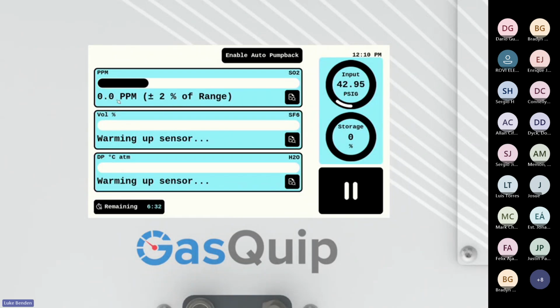Right now we're getting 0.0 parts per million of SO2 in this particular test. This accuracy, in the parentheses, is just an accuracy rating for the test itself. We put that in there as a way for the user to understand that you may or may not be falling into the tolerance of the sensor itself. So for example, if you're testing a bottle of gas and say you have 99.9% purity on this bottle of gas that you're testing, well, the accuracy of the SF6 sensor is plus or minus 0.5%, meaning that if you test that bottle of gas and you get a 99.5% readout on that, you know that you're within that tolerance or accuracy of the sensor, and you know that your gas is passing your spec or meets what you thought it was going to meet.